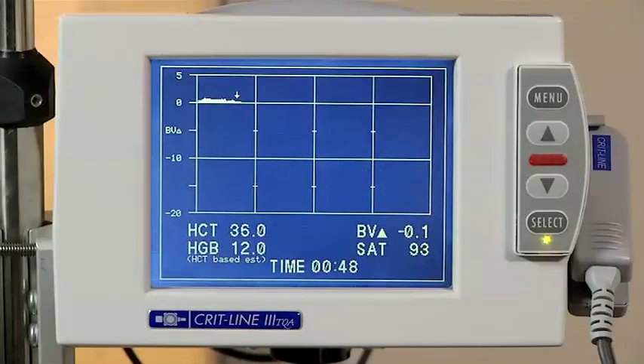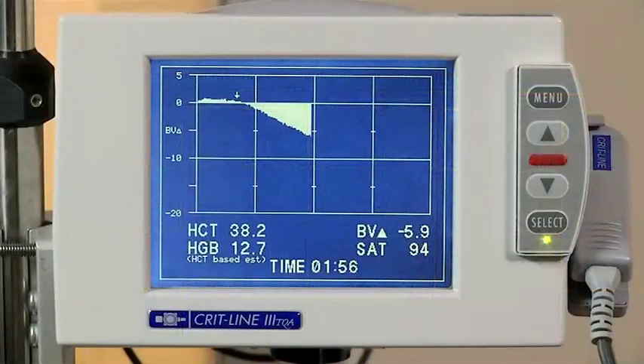In the example here, the profile begins to decrease gradually starting at 1 hour. The decrease is greater than 3% per hour, but less than 8% per hour. This is considered a B profile. The ideal slope is not a fixed percentage of BV decrease and will vary from patient to patient. In the example, the operator has marked an intervention at 45 minutes into the treatment. To mark an intervention, press the up or down arrow anytime during the treatment. The marker can be used to remind you that an intervention was done at that time.